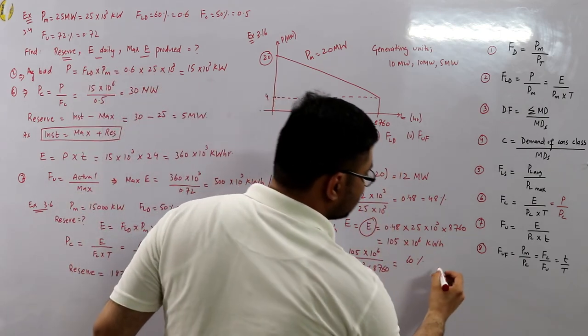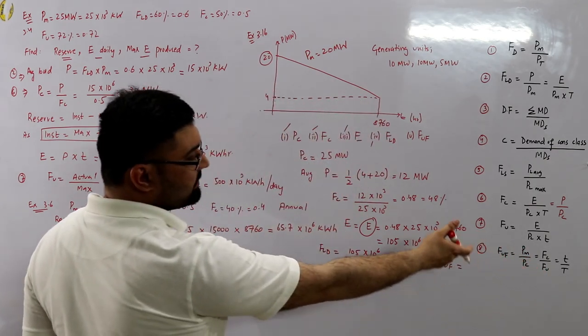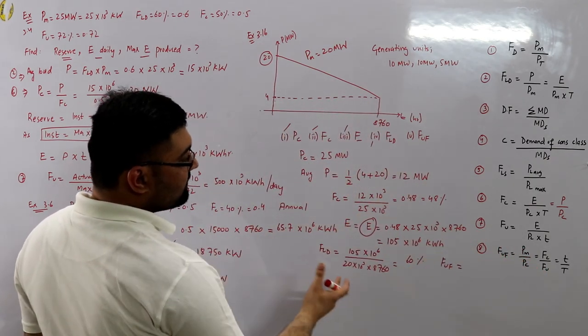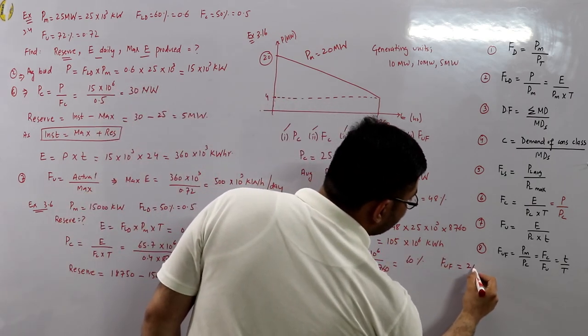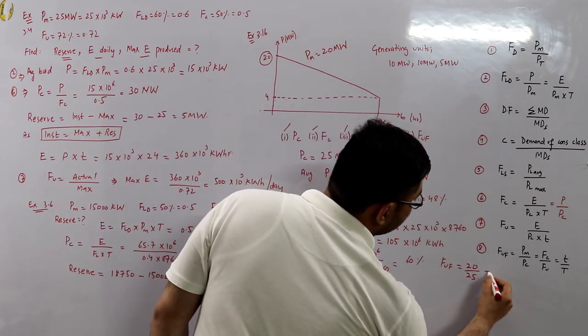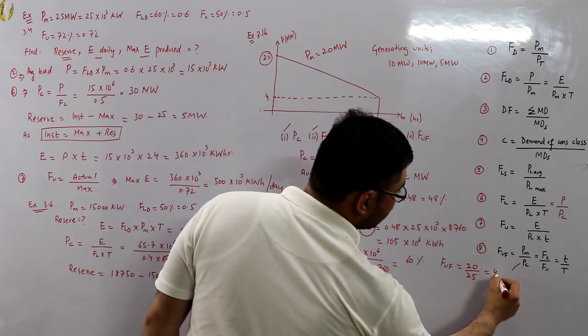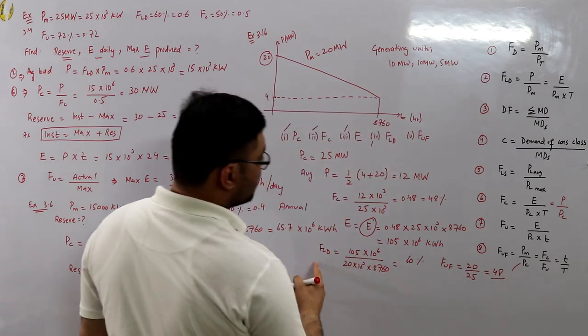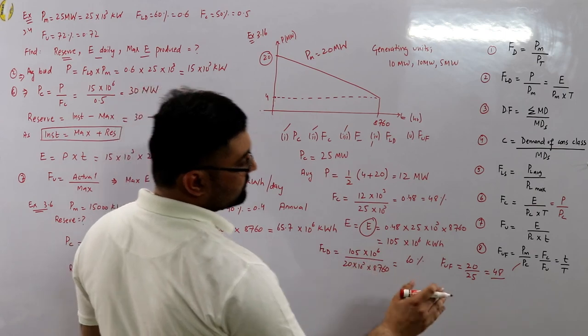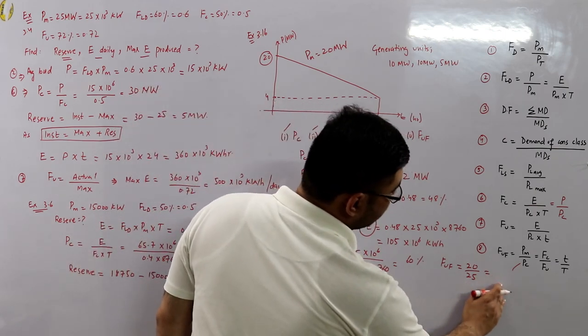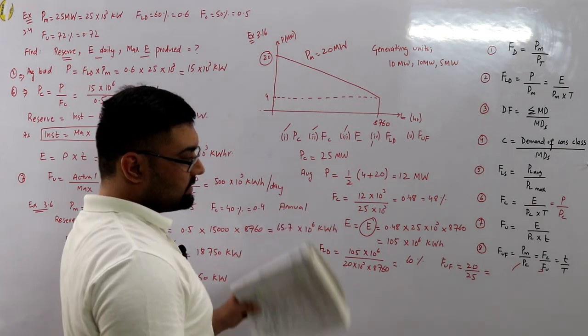The utilization factor F = PM ÷ PC = 20 megawatts ÷ 25 megawatts = 0.8, or 80%. We cannot use the FC ÷ FU formula here because FU is not given.